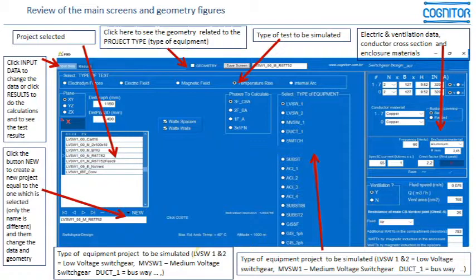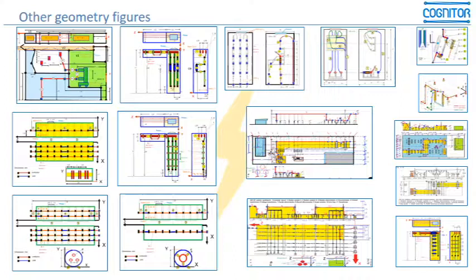On the right side you have a list of electrical and ventilation data like conductor cross-section, materials of conductors and the enclosures. You have rated currents which will be applied in the temperature rise test, and all data which will characterize the project. Isolators and expulsion type fuses are used only for customizing the project for specific clients and are not available in this version of the software.